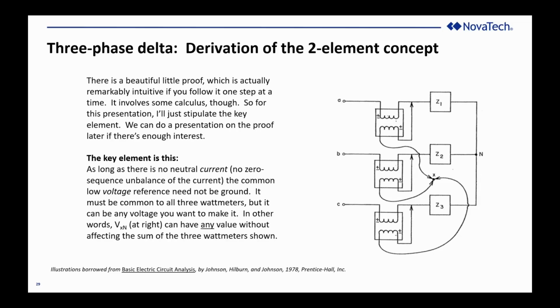Now, here's where I have to take a step back. I mentioned that the proof in my sophomore textbook is very beautiful and very intuitive, but it does go into the calculus behind this assumption. So I'm not going to go into the calculus in the context of this. I could do another presentation, wouldn't take very long for people who are interested, but it basically comes down to one assumption, and that is if there is no neutral current, no zero sequence unbalance in the current, then we can move the common reference point for all 3 voltages, for all 3 wattmeters. We can move that off of the neutral, and as long as we don't separate them, we keep a single point X that's the reference for all 3, the voltage between that X point and the neutral point is no longer a factor in measuring the total of the 3 wattmeters to be the total 3-phase watts.